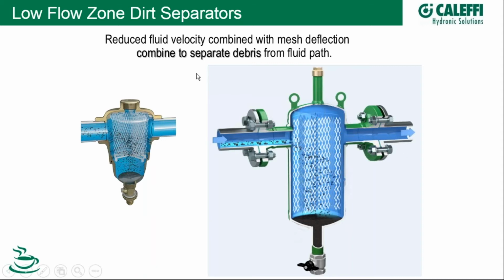So how they work is, as fluid velocity enters the separator, it slows down by a factor of about 9 or 10 to 1. If we have 10 gallons per minute coming in, it slows down to 1 gallon per minute as it goes through. And simply by gravity effect, debris starts to drop out.